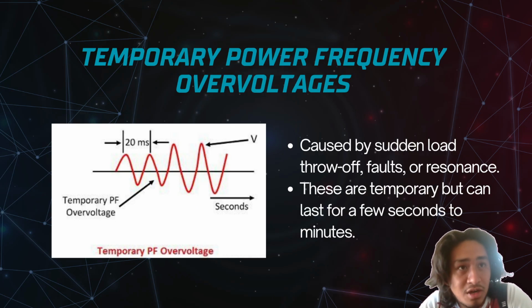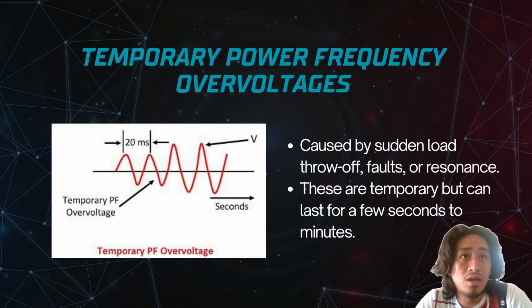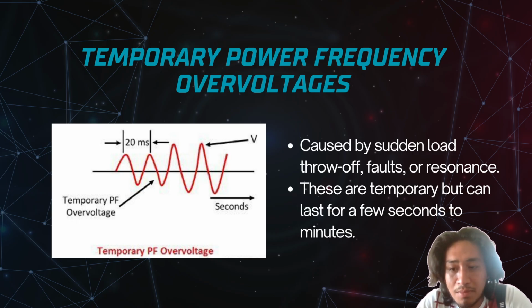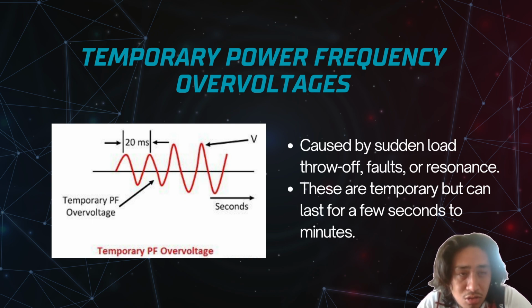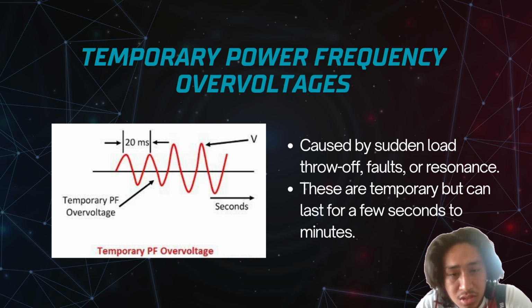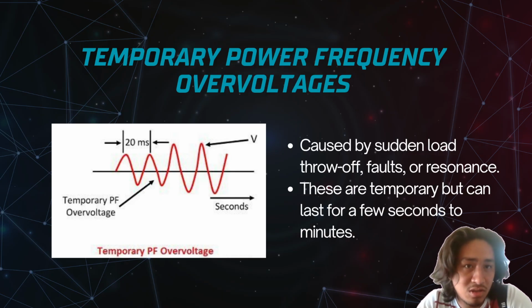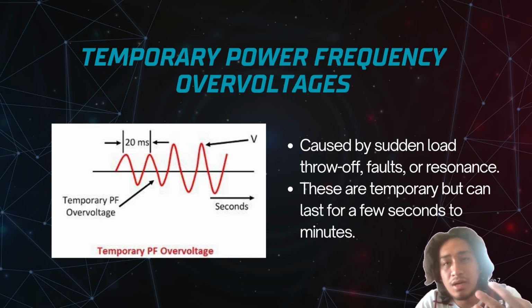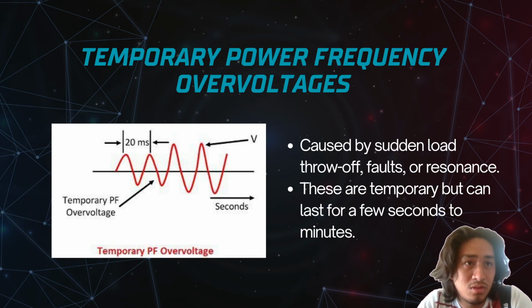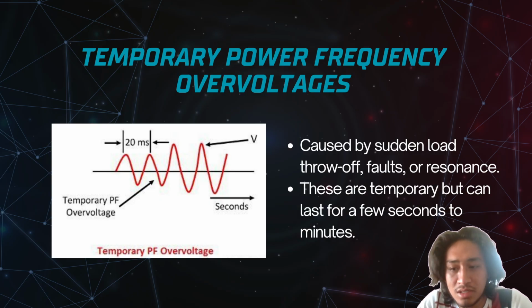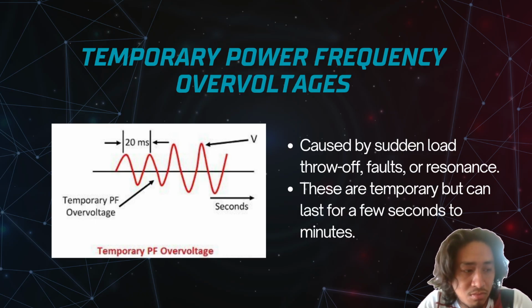So as I mentioned earlier, with insulation breakdown, your insulator becomes a conductor, and this can be mitigated by proper earthing and surge protection. So the solution to this is surge arresters. Surge arresters are designed to absorb this energy. So instead of the energy going into your system and causing damage, the surge arresters absorb it. As mentioned here, they are designed to absorb this energy, and effective grounding reduces the magnitude. So some of the magnitude goes to the ground.